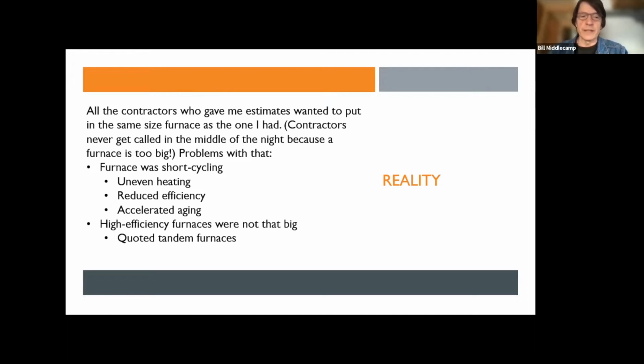It was far too big for the ductwork that they put in the house when you were only heating one floor at a time. And when it runs where it starts and stops frequently, you have reduced efficiency when it starts up, so that overall efficiency of the furnace is less, and it accelerates the aging of the furnace because every thermal cycle stresses the metal, and I think that's why the furnace that was in there only lasted 13 years. The problem with the two was, if they're going to put in another furnace and I wanted a high efficiency furnace, they were going to put in 2 furnaces because high efficiency furnaces don't come that big. The biggest one I could get in a Lennox Pulse, which is what I ended up with, is 80,000 BTUs. And I wanted to see if I could use that furnace. Next slide.